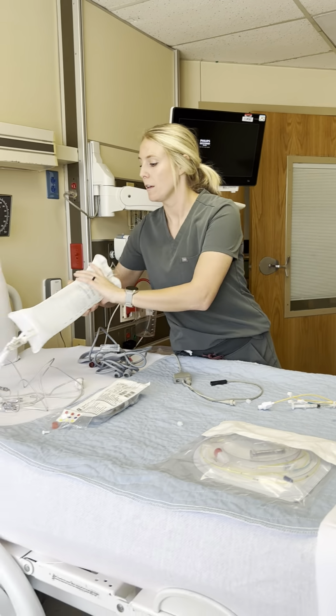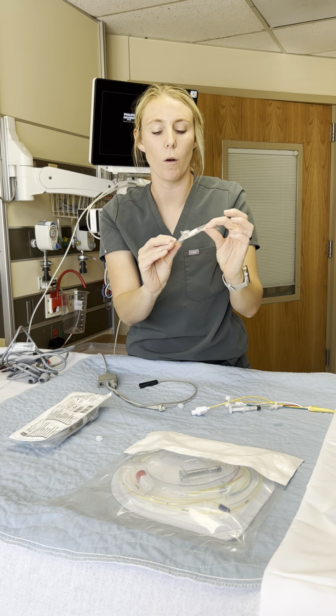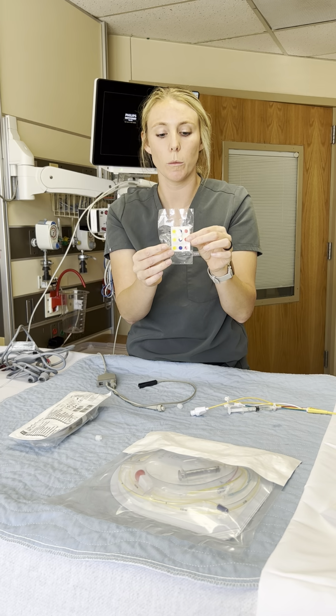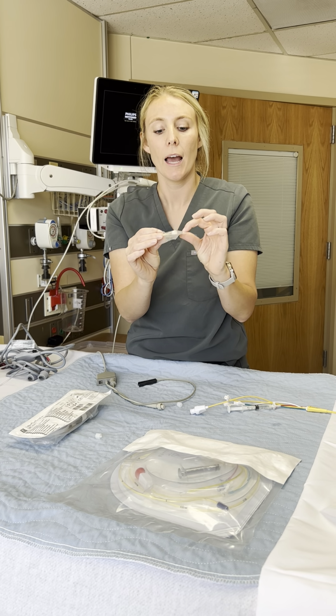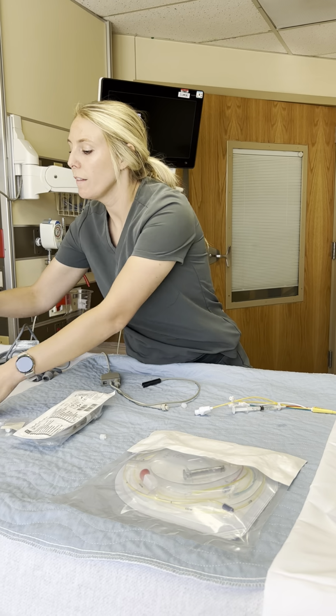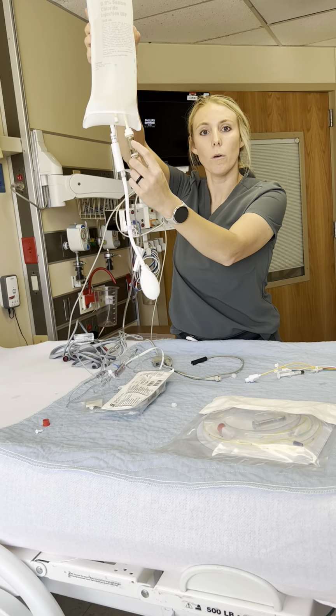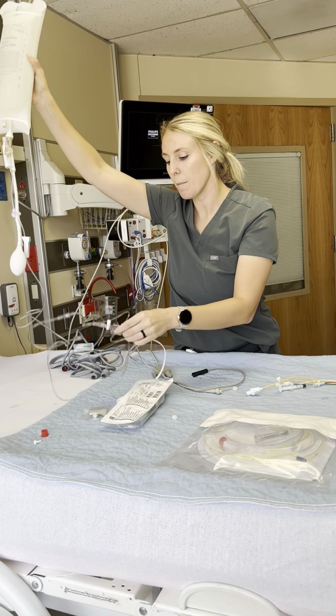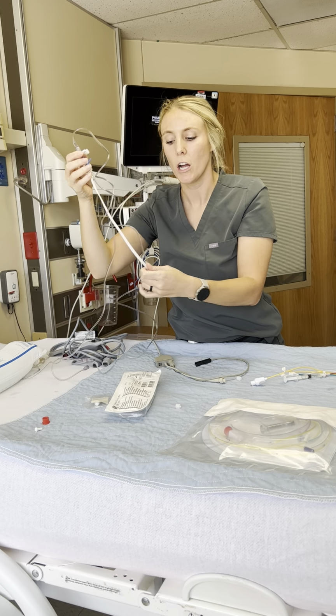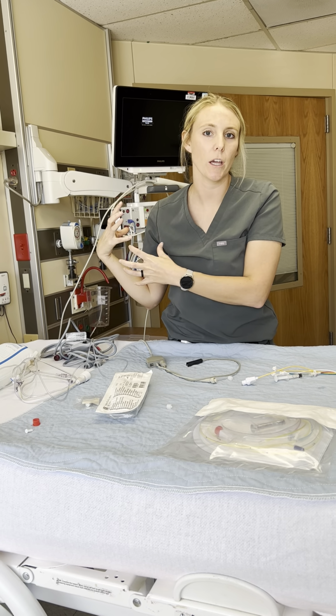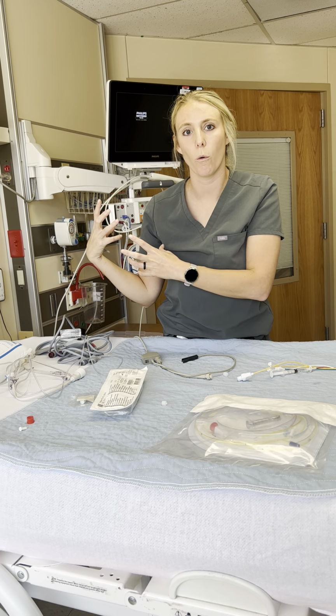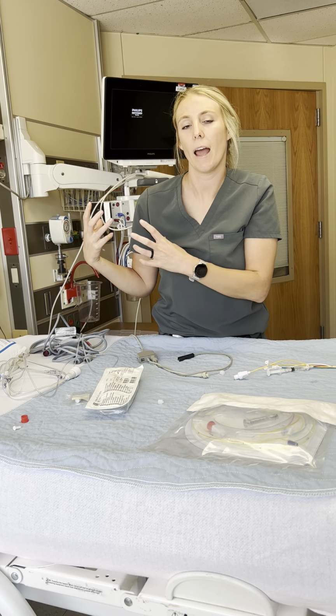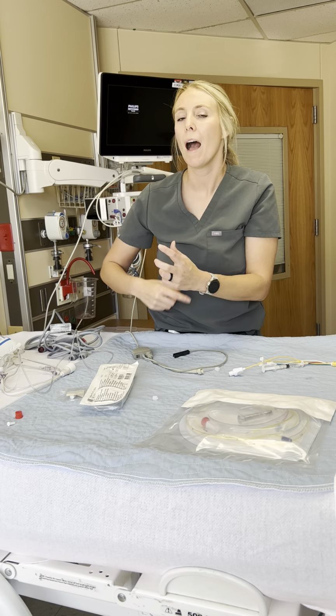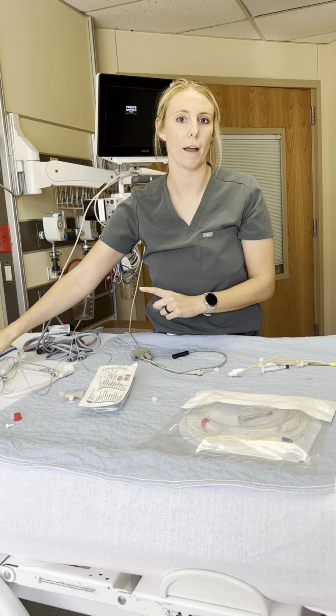So when you open your transducer bag, do not throw your labels away. I know every time we open them, we throw them away. This is where it is extremely handy. Blue is for CVP or right atrial pressure, yellow is for the pulmonary artery, and red is for arterial. So when you're getting these ready, you should label this with a dot, and label your stopcocks with the appropriate color so that when all of this tubing is beside your patient and rolled up in a ball and you're troubleshooting why you don't have a waveform, you can easily see, I'm not having an A-line waveform, I'm not having a pulmonary artery waveform. I can troubleshoot that all the way back up into my pressure bag, okay?